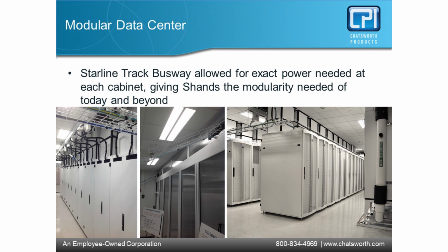And actually, one of the benefits of deploying busway is, if you are using underfloor today for power distribution, a lot of times you can come in, install the busway overhead, and then start to cut over things live, or in planned outages and things like that. So you do have the flexibility to do that. So yeah, we are seeing a lot of these legacy facilities that either need to be upgraded just because of limitations of the infrastructure that's in place, or they're going through a refresh of that space. So yeah, definitely see that.